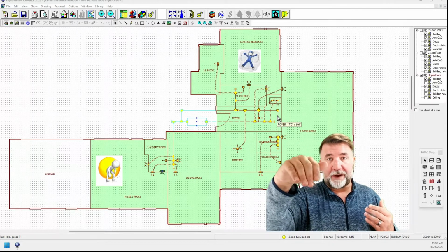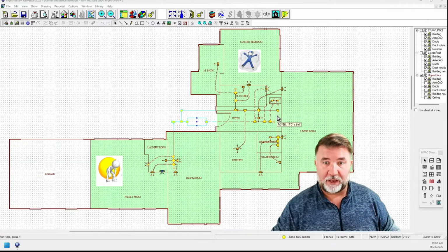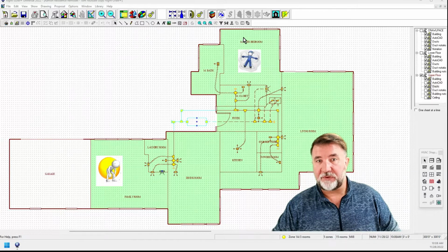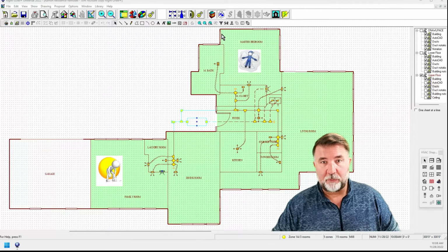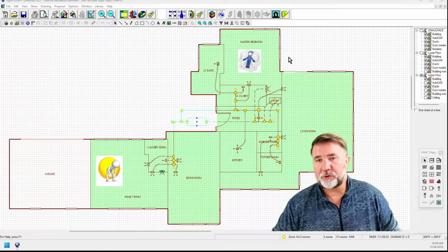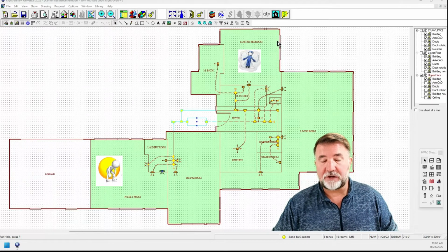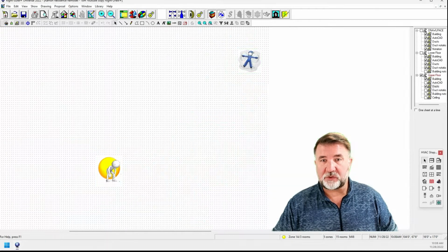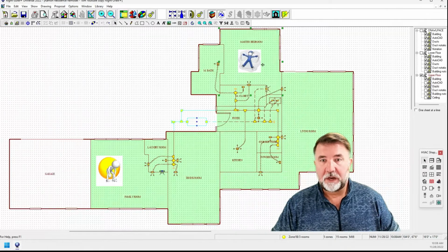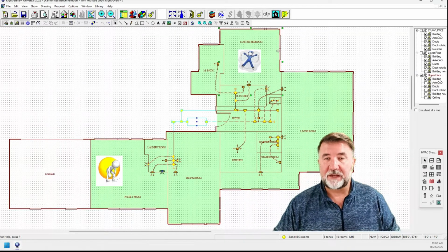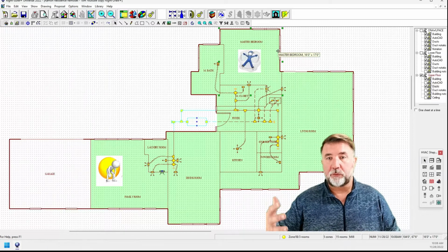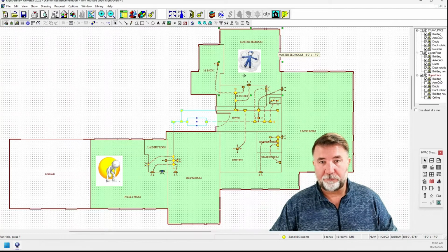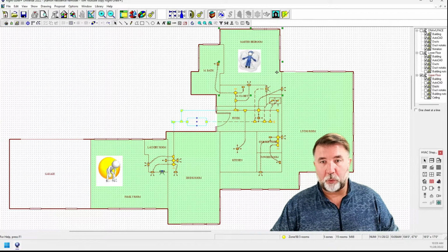Okay? Because what we need to be able to do in these rooms is mix the cooler air, the 50 to 55 degree air that's coming out of the supplies. So this supply duct right here is going to be blowing out 50 to 55 degree air if we're air conditioning. And it's going to hit these walls and do what's called wall washing. So we have the heat penetrating these walls and windows. And as that heat penetrates, we want to take this cooler air and mix it with the warmer air coming through the walls and windows by heat loss, heat gain. So when we mix that, by force, we're circulating and pulling that air back around.